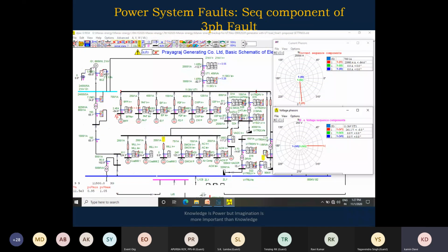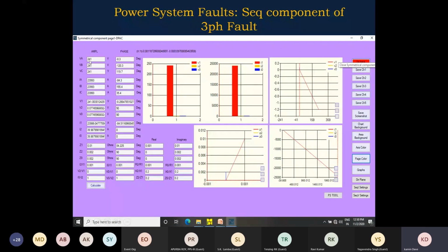Now, if you look at the symmetrical components, the positive sequence current is 23.993 kiloampere at minus 84.6 degrees. Negative and zero sequence current is almost zero. Similarly, the positive sequence voltage is 241 volt at minus 0.3 degrees, and negative and zero sequence voltage is 0. So you look at it here, the positive sequence component is significantly high. The negative and zero sequence components are very low, almost 0. So look at it here, the sequence component is 241, 241, 241, VA, VB, VC voltage. Now you see the V1 voltage. V1 is the positive sequence voltage, 241, V2 is 0.07, V0 is 0.07.